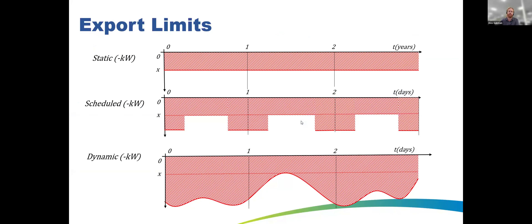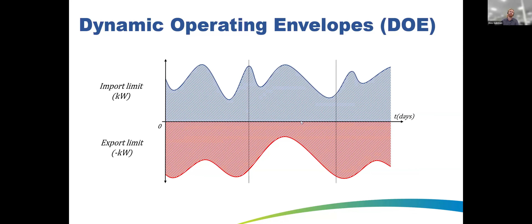Traditionally, export limits have been a static limit that didn't change over time. We're moving towards dynamic, which is updated in real time based on the current network constraint — generally meaning customers can export more than they would under a static limit. We also use the term 'scheduled' for something halfway between the two, like a time-of-day schedule but not exactly real time. It's called a dynamic operating envelope because an envelope has two ends — in addition to an export limit, you can equally have an import limit on the other side, applying to controllable loads.